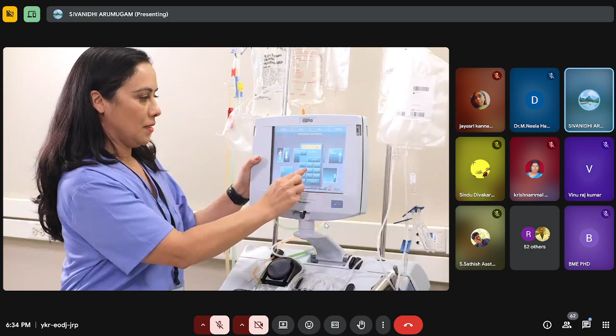It has two ways. One to connect AC. So here this orange color and this black color one is called the detector. This is the AC detector. For example, now I'm connecting AC, but I didn't open the clamp, meaning I'm not opening that AC tube. If I'm not opening it, then the AC won't be mixing with the patient blood. So that is the risk. To prevent that, we have this AC detector here to detect the flow. On the backside we have the AC bag connected, and this detector will detect whether fluid is passing or not. If it is not passing, it will raise an alarm. Alarm means it will notify the operator with sound and light.